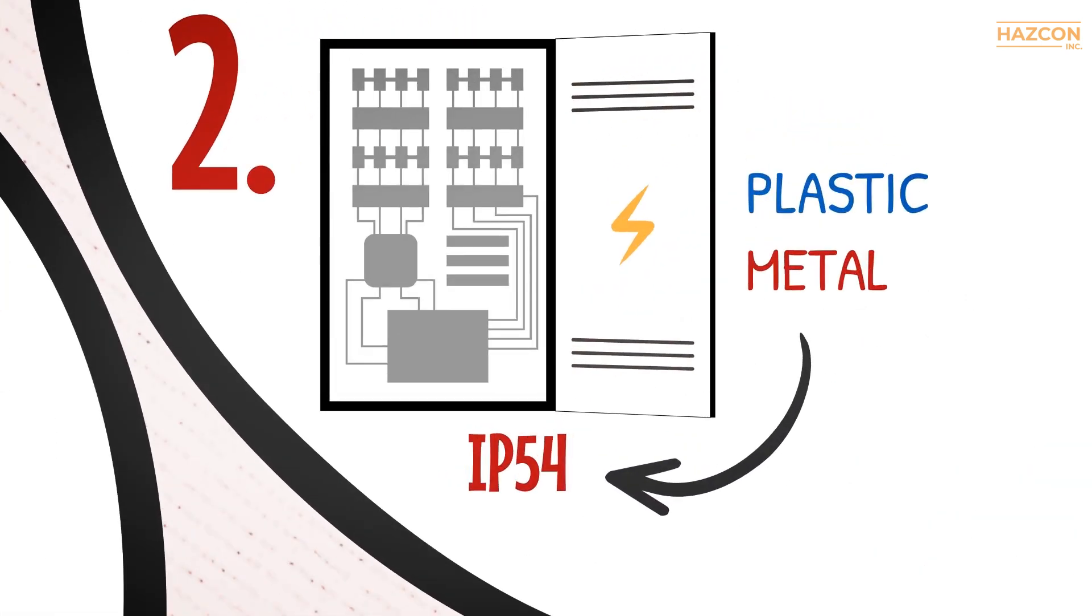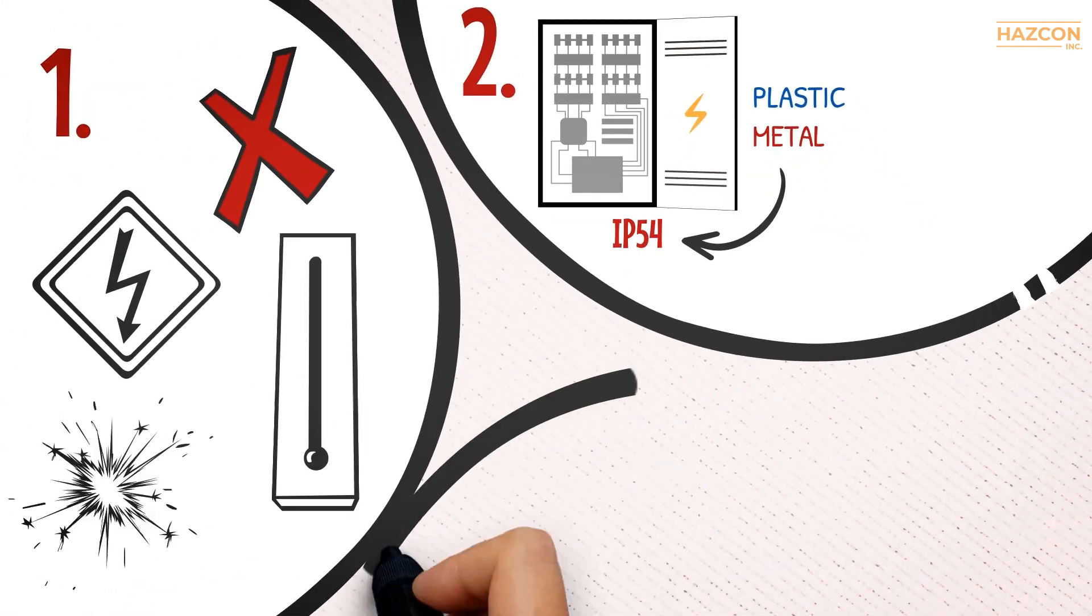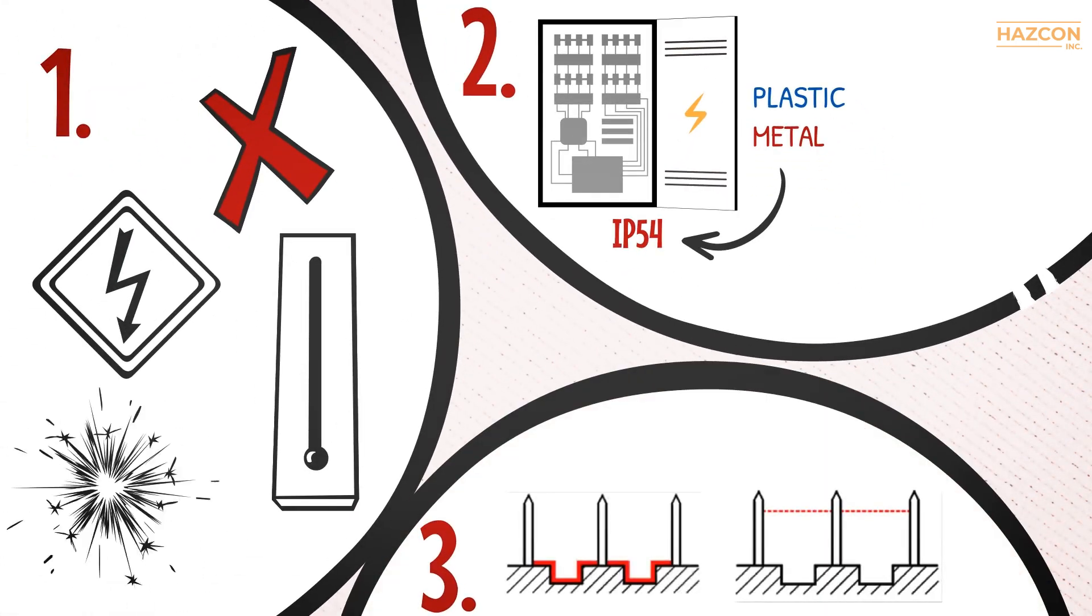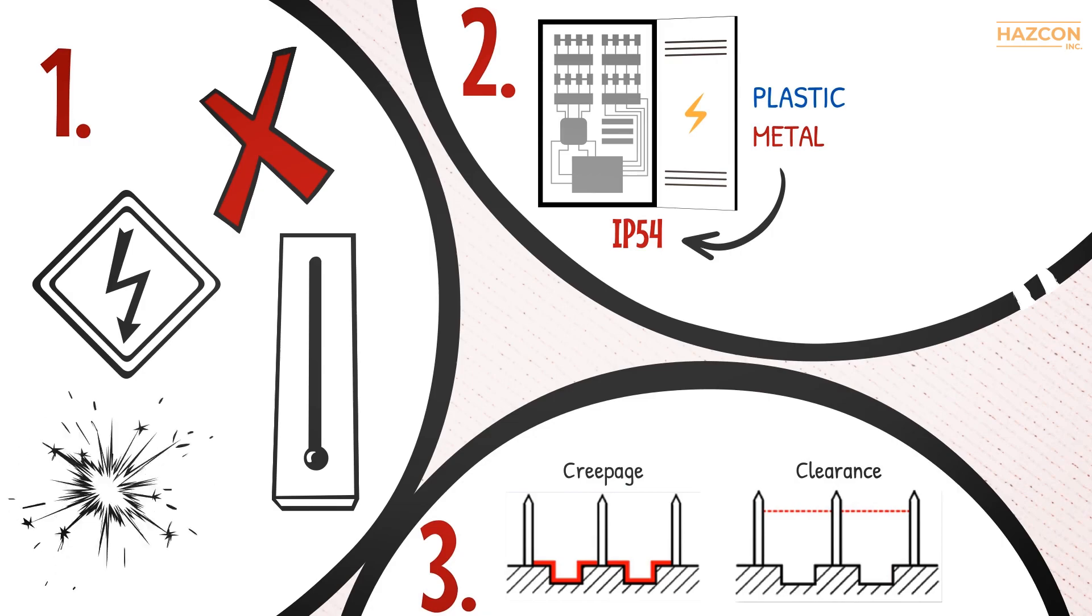Keep in mind that if a flammable gas or air mixture is ignited inside an Ex e enclosure, the enclosure is not designed to withstand the explosion. Creepage and clearance between the bare conductive parts must meet the requirements of the standards.